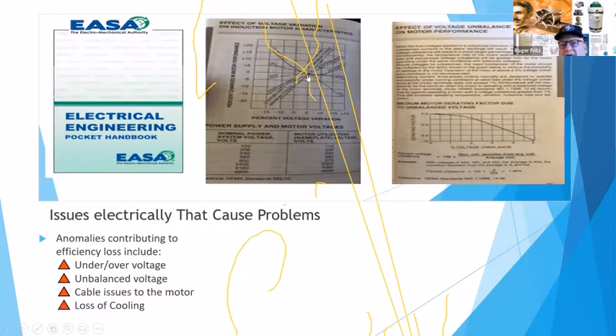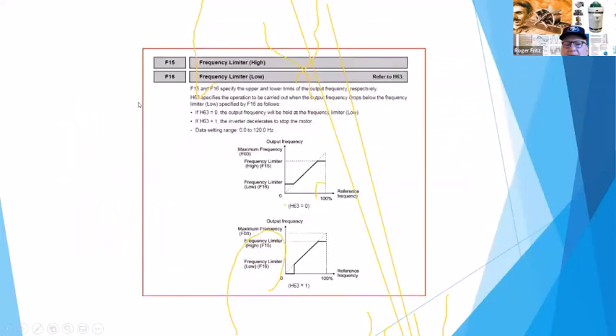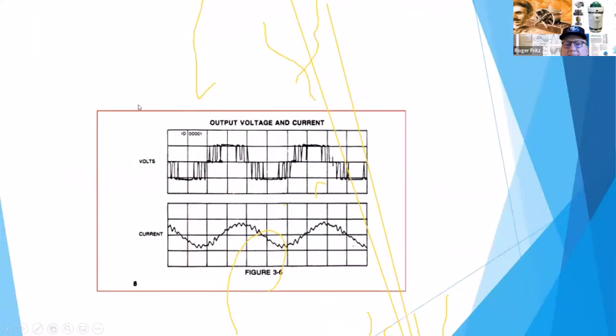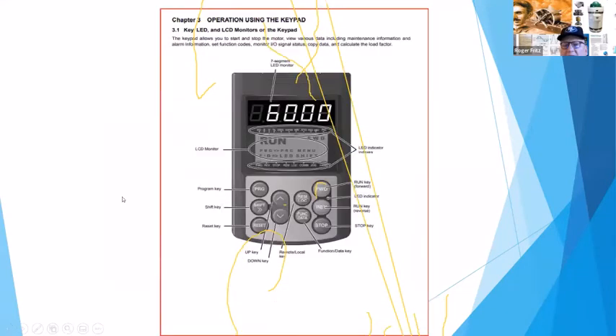It also, over here, this chart shows that a motor winding was originally designed to be at its best magnetic point, which was what the nameplate said. So if it's 460 volts, as it goes higher or lower, then the heating factor inside the motor becomes warmer and warmer. Plus, with the implementation of PWM on the output voltage here, you don't get perfect clean sine waves. So you end up creating additional loss factors.